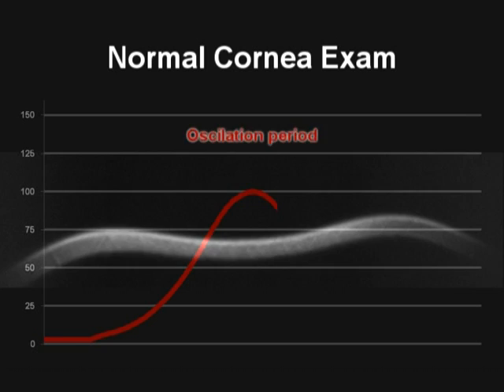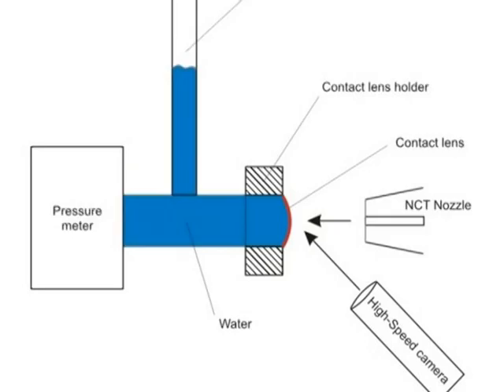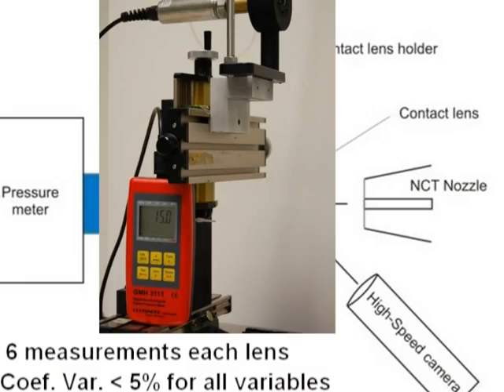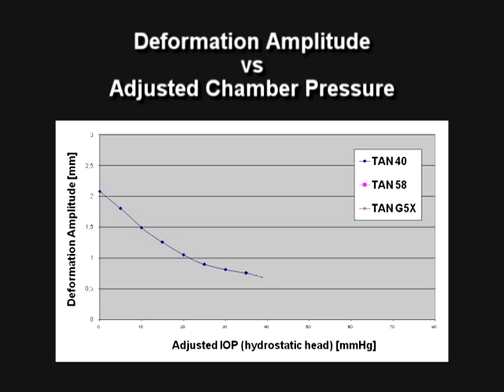The Oculus Corvis ST is a new system that combines an ultra-high-speed Scheimpflug camera to image an 8mm horizontal meridian throughout corneal deformation during non-contact tonometry. An experiment was performed using different types of hydrophilic contact lenses mounted on a sealed, tightly controlled pressurized water chamber. The pressure was set from 0 to 70 mmHg with 5 mmHg intervals. The deformation amplitude, related to the stiffness of the lens in the system, was tabulated along with other variables. Each lens had a different deformation behavior.